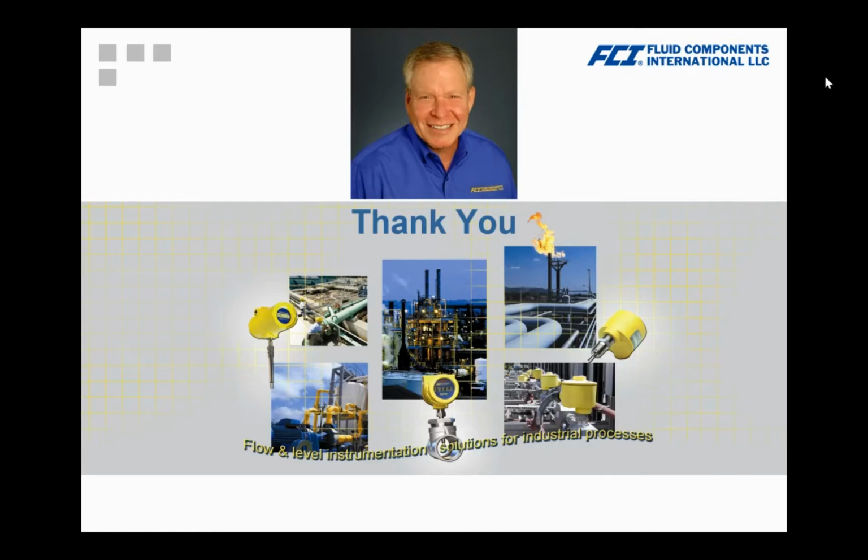One is the alignment parallel to flow. How critical is that? If you're within 5 degrees, typically you can eyeball getting that in, and it's not going to affect accuracy. If you're rotating and you go more than 5 degrees in one direction or the other, it's going to begin to affect accuracy at a rate of, let's say, 1%, from 5 to 10 degrees.